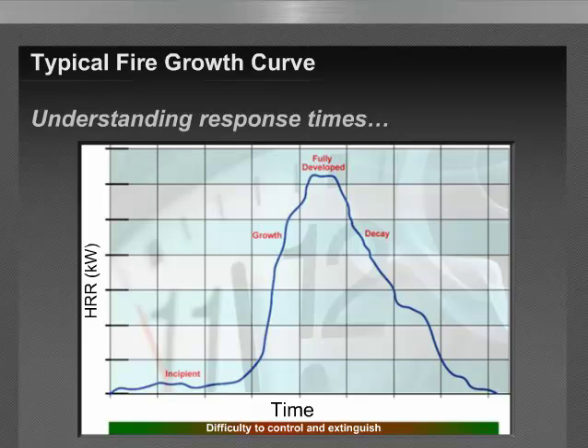So on this particular chart, fire progression, we look at the various stages of fire, which is comprised of four stages. This includes the incipient, growth, fully developed, and decay stages. As we look at the incipient stage, which quite frequently could be the progression of equipment or component degradation or failure, overheating of cabling, and similar such events, in some cases it could occur over the course of hours or even days before the outbreak of flame ignites.